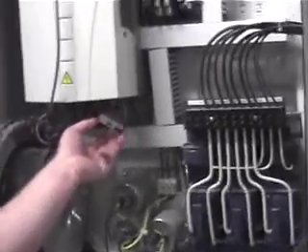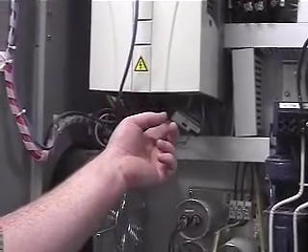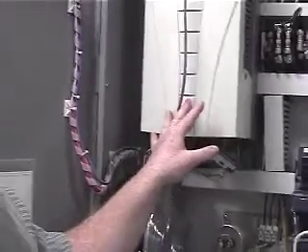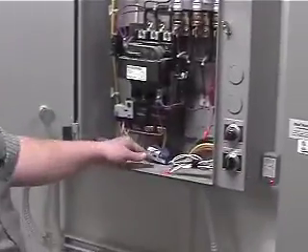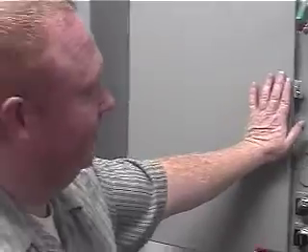All the VFDs we're measuring, so all the VFDs have a transducer, and what we're doing is we're actually measuring the current draw through it. All the pumps that are just on the starter, like an HOA switch, actually use current switches, so it's just off or on. You're probably pretty familiar with those, right? So does that take place on those round donuts that used to be on them to read the actual circuit? Yeah, so this one still has it. And this is just a switch, it's just on or off. And so it'll just say pump running or not, just pretty standard.